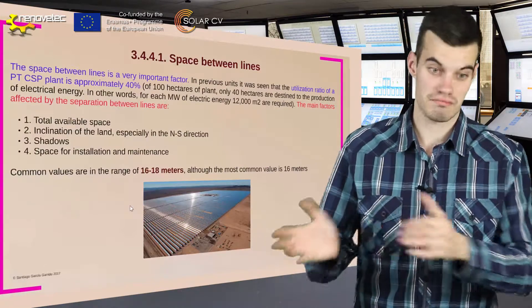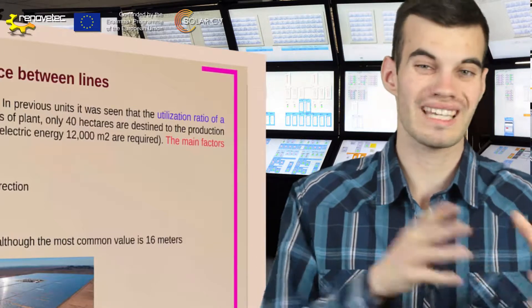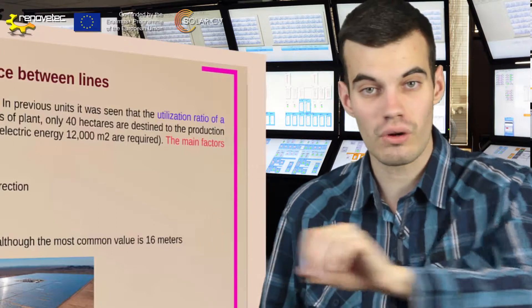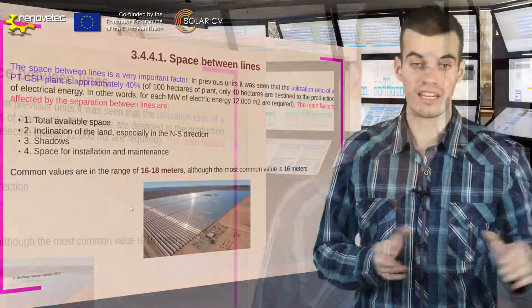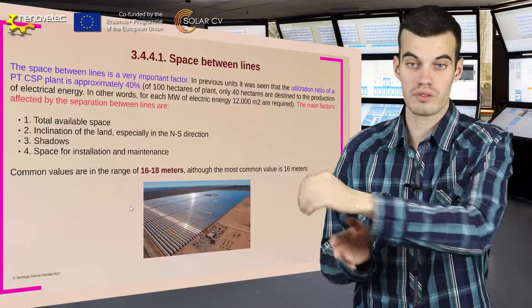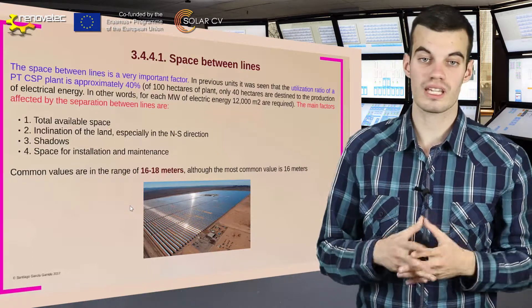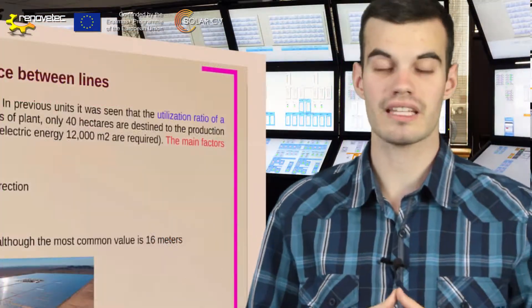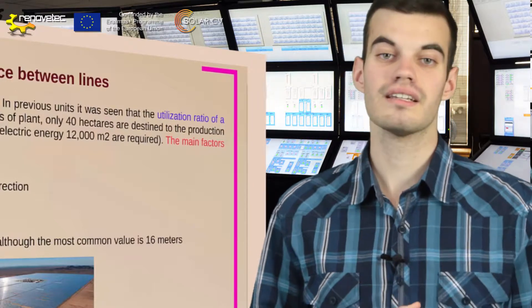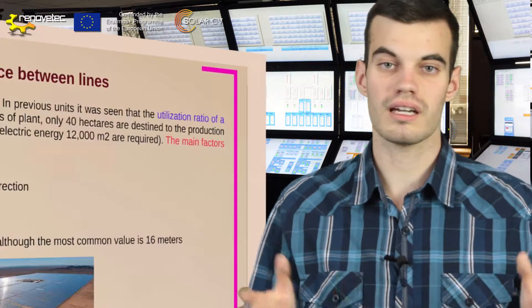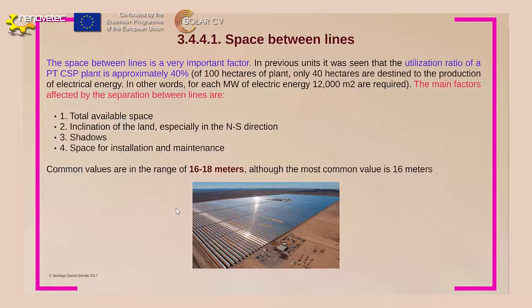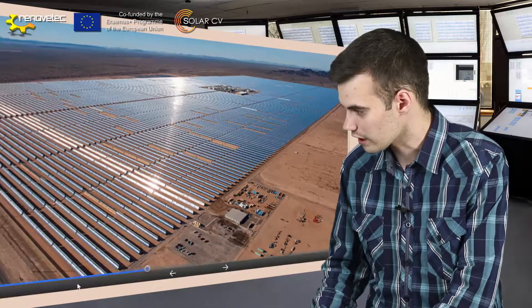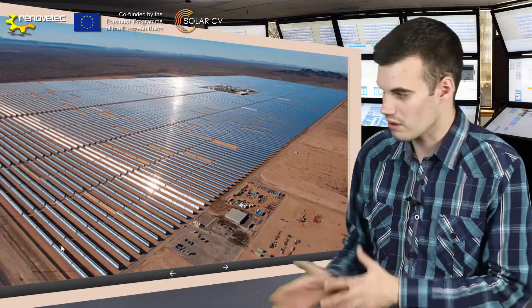The main factors affected by the space between lines are: the total available space, the inclination of the land especially in the north-south line, because the main orientation system is east-west so the loops go in the north-south line; the shadows, because we don't want any shadows on other parabolic troughs to improve performance; and finally the space for installation and maintenance, because each module must be cleaned of dust particles and bird droppings. Common values are in the range of 16 to 18 meters, although the most common value is 16 meters. Here we can see an example where the space between lines is more or less 16 meters.